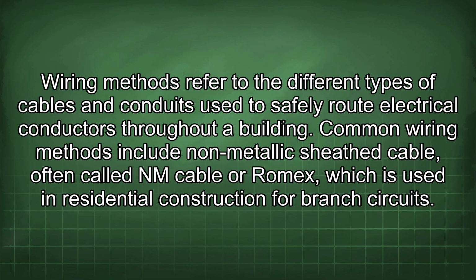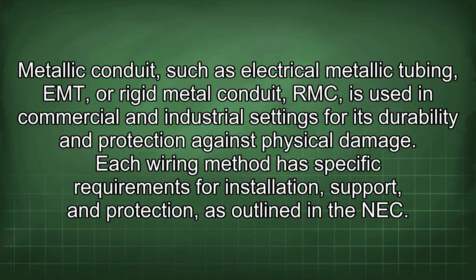Wiring methods refer to the different types of cables and conduits used to safely route electrical conductors throughout a building. Common wiring methods include non-metallic sheath cable, often called NM cable or Romex, which is used in residential construction for branch circuits. Metallic conduit, such as electrical metallic tubing and rigid metal conduit (RMC), is used in commercial and industrial settings for its durability and protection against physical damage. Each wiring method has specific requirements for installation, support, and protection, as outlined in the NEC.